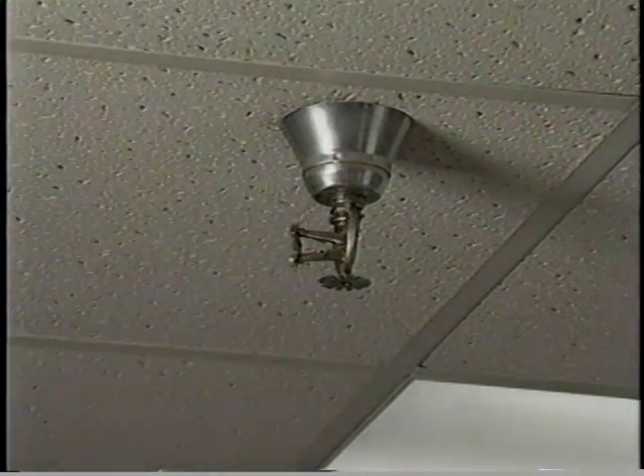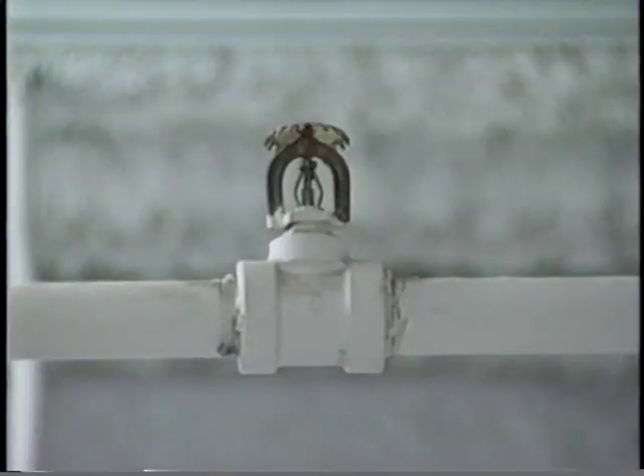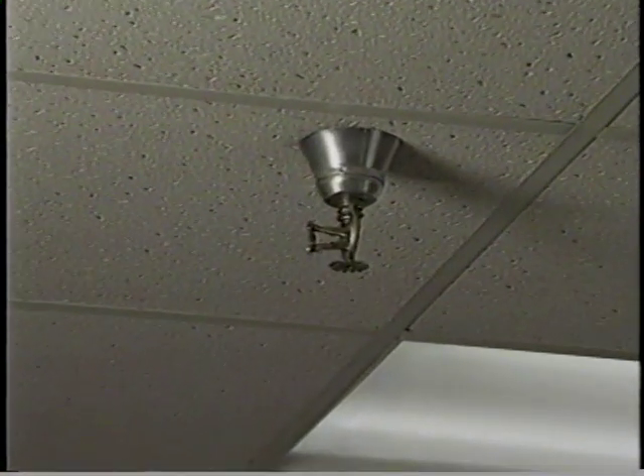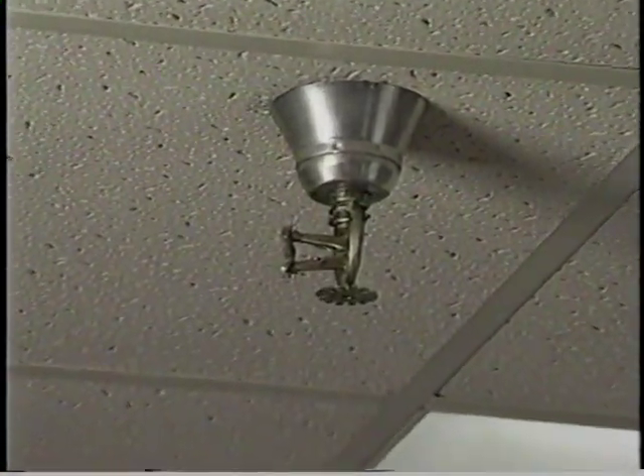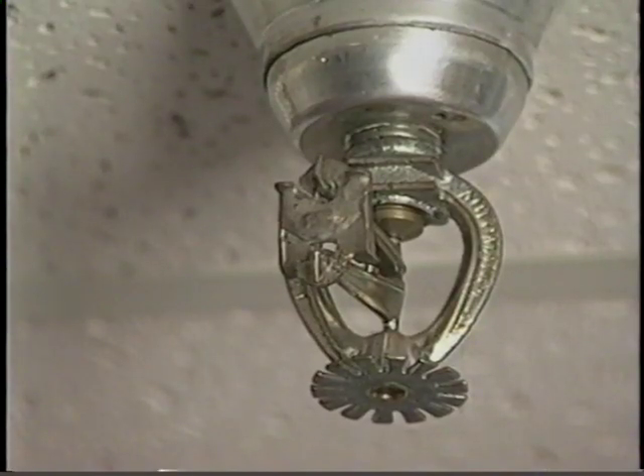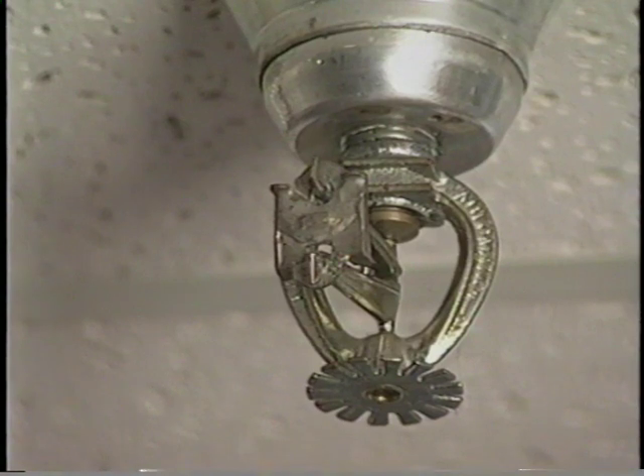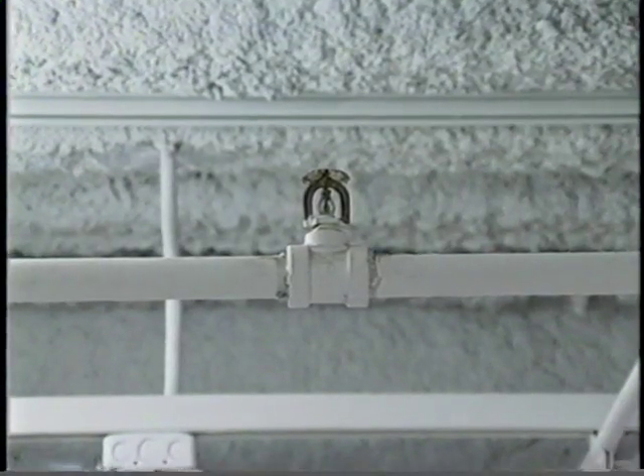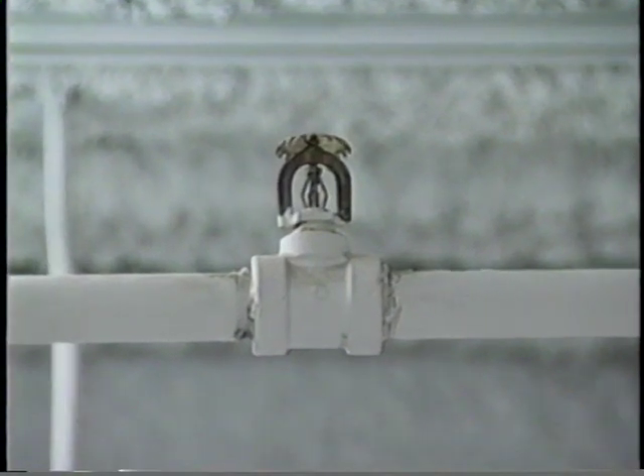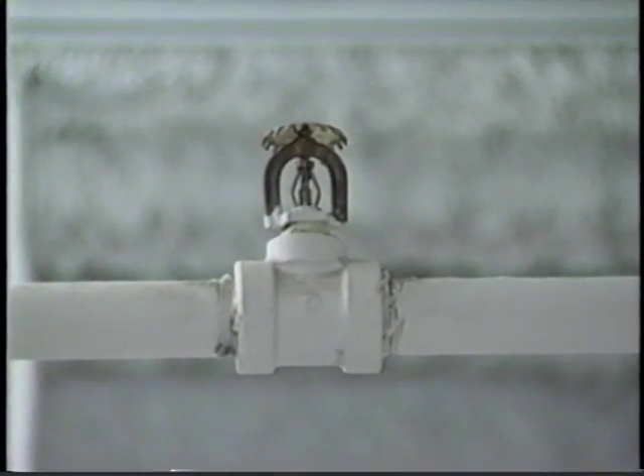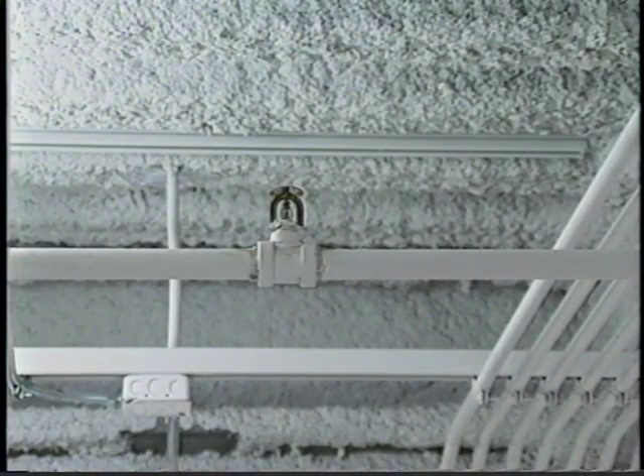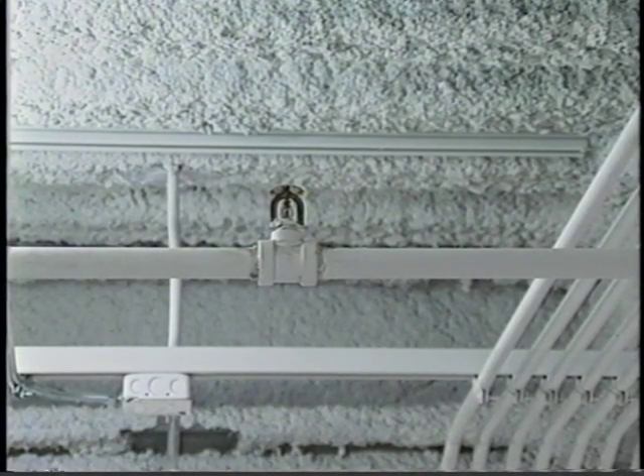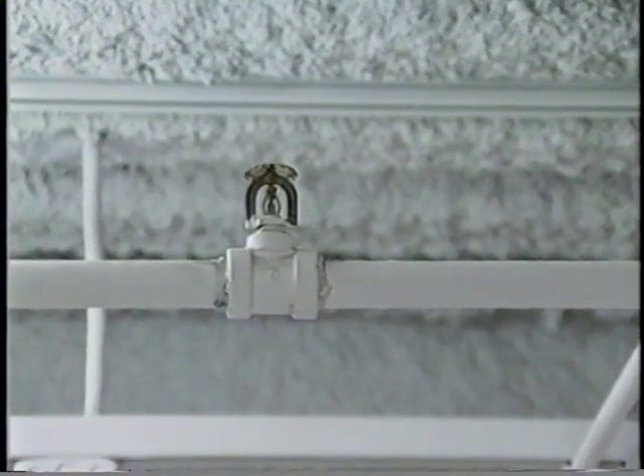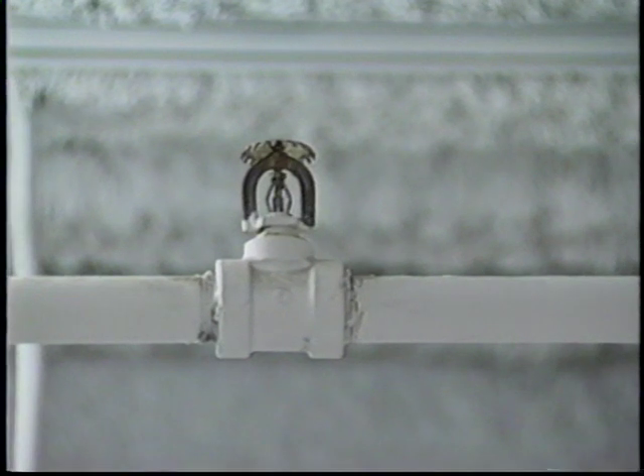There are three basic designs for sprinkler heads: pendant, upright, and sidewall. The most common type is the pendant sprinkler, which extends down from the underside of the piping. This sprinkler sprays a stream of water downward into a deflector that breaks the stream into a circle. The upright sprinkler sits on top of the piping. It sprays water into a solid deflector that breaks it up into a circle that is redirected toward the floor. The upright standard sprinkler cannot be inverted for use in the hanging or pendant position, because the spray of water would be directed toward the ceiling.